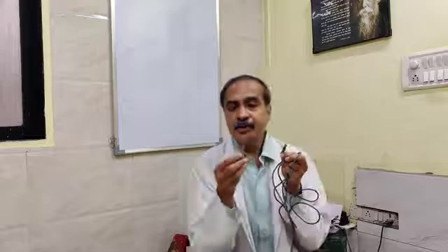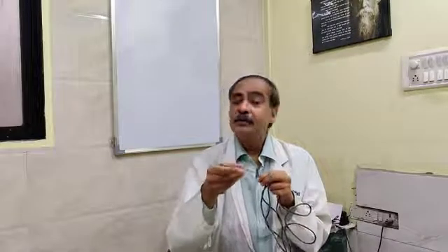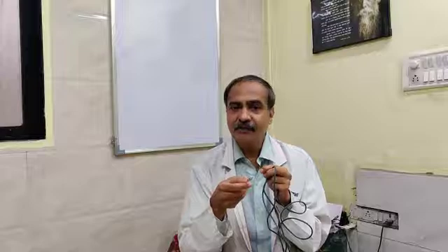Now to this connector there will be a loop or any active electrode like ball electrode, hook electrode, where the active electrode has got a long active arm which goes into the high frequency cord, because on the high frequency cord on the right side there is a hole through which the long active arm of the active electrode goes into it.